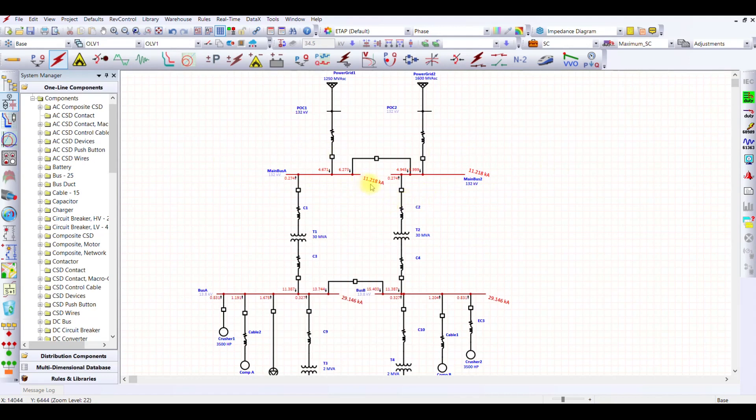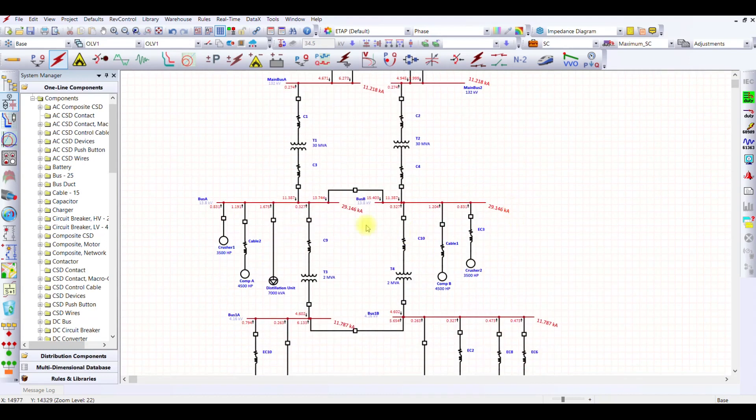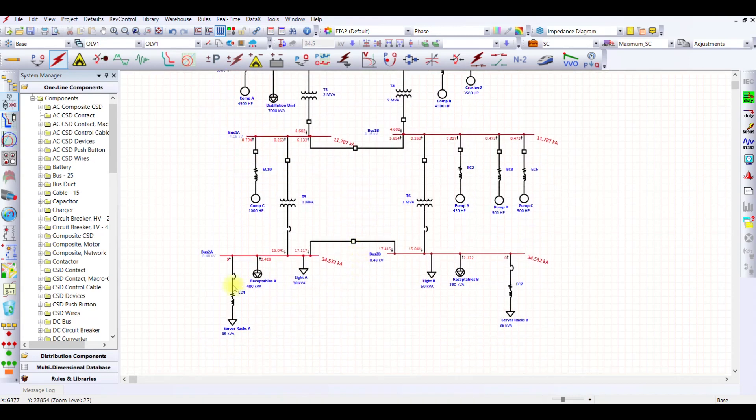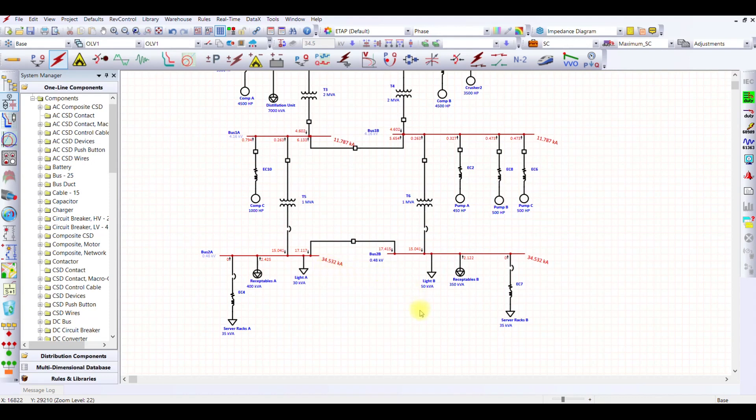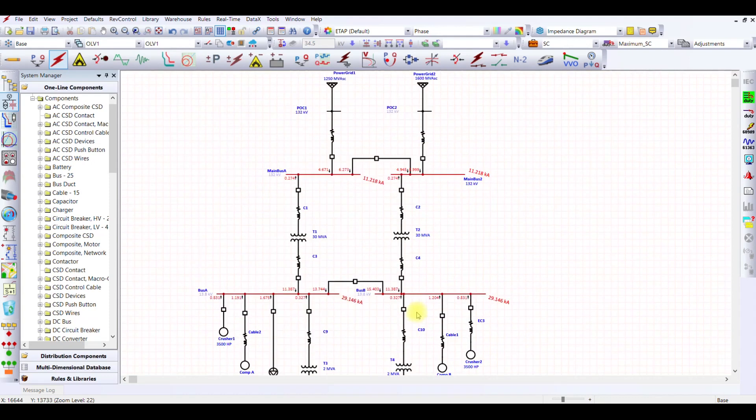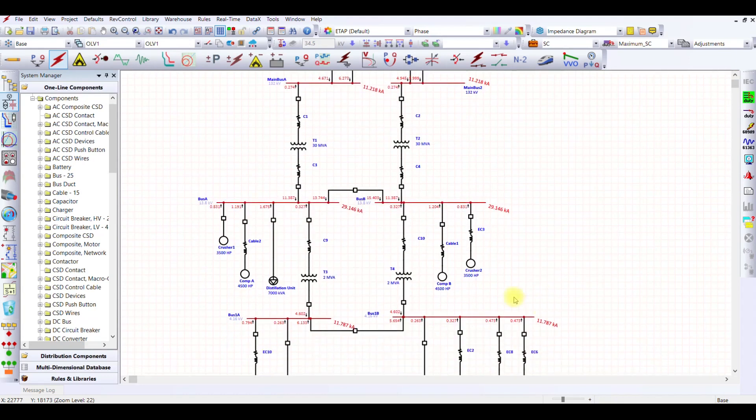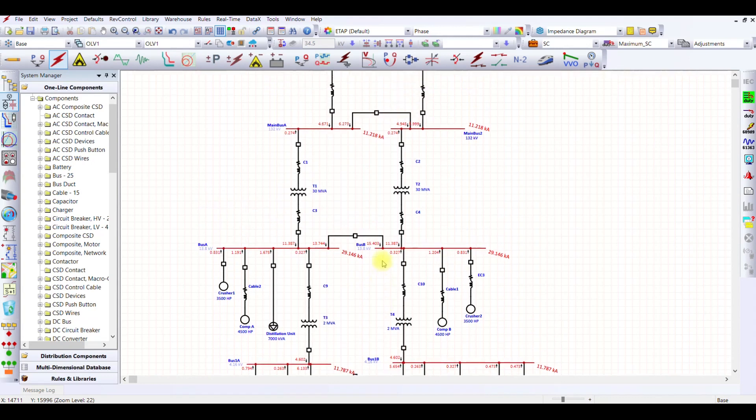At my 13.8 KB bus, my short circuit level is 11.21 kilo ampere. Similarly at my 4.16 KB bus, my short circuit level is 11.77 kilo ampere. And at my LV bus which is 0.48 KB bus, my short circuit current level is 34.5 kilo ampere. This means that if I want to select bus, at least my bus bar should be able to withstand this much amount of short circuit current. And you can also see the contribution coming from each motor or my lump load.